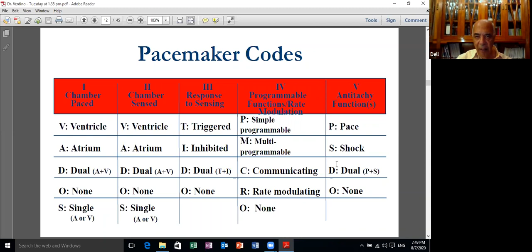And the third is the response to sensing: triggered, if an impulse in one chamber triggers an impulse in the other chamber, inhibited, dual, or none. And the fourth letter is actually R. All of this has been removed completely because all the pacemakers available now are multi-programmable and they are communicating. So they are either rate responsive or not rate responsive. So we have 3 letters and an R occasionally, and we don't have the 5th letter, which is now a description for the ICD.